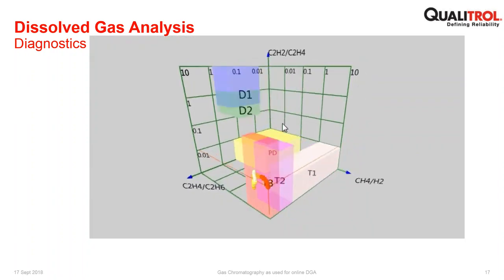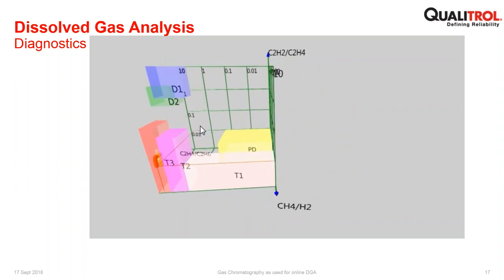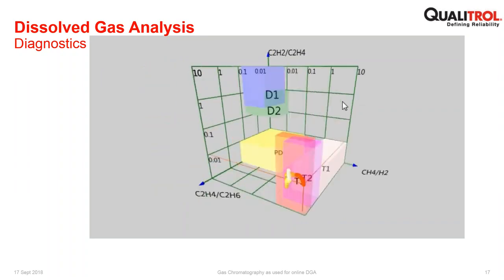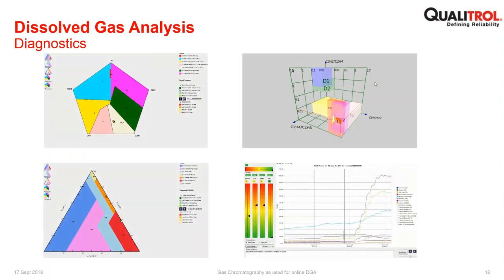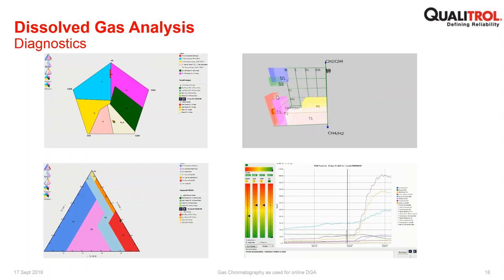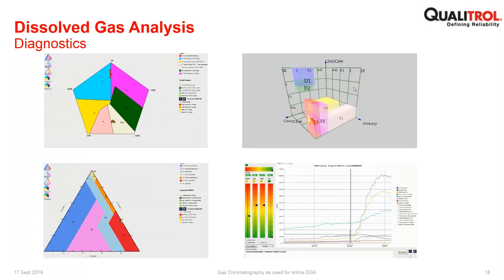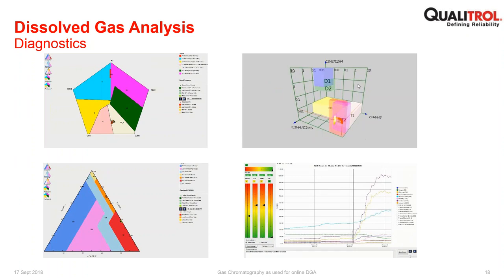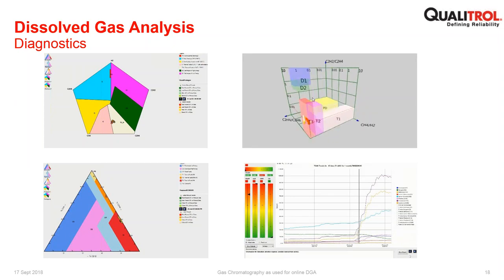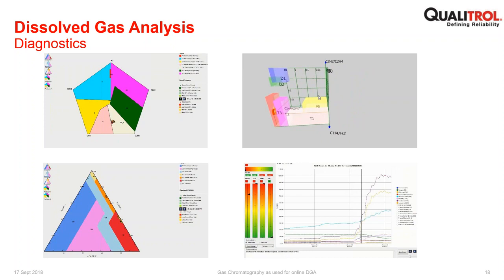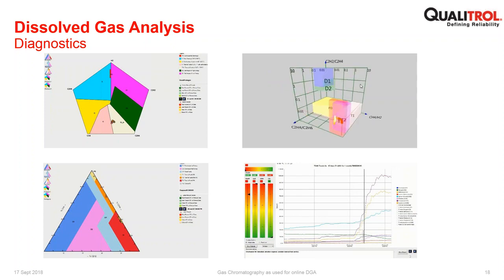This is a graphical representation of Rogers ratios. Again, it's a coordinate point looking at 3 different gas ratios and presents then a diagnosis. And all of these graphics are contained within the software that you will get with an online DGA system. So this is what you see with the Qualitrol system. Other systems will likely incorporate most of these diagnostic systems in a similar graphical format. The one unique to Qualitrol will be the one on the bottom right-hand side, which is Tone, and that's the artificial neural network system. A very powerful system for understanding and for alarming based on a diagnosis rather than based on parts per million or based on rate of change. This will alarm based on an actual diagnosis.